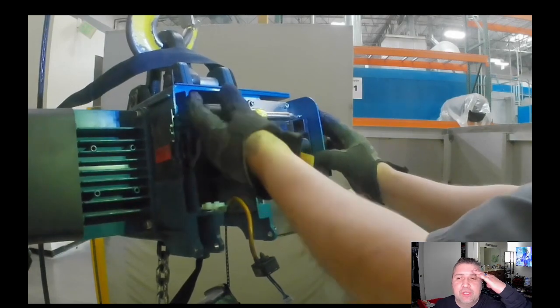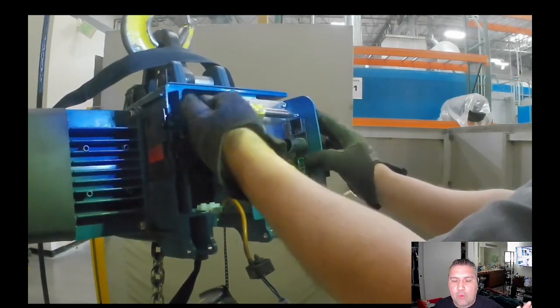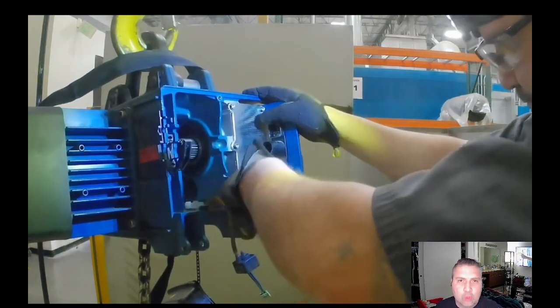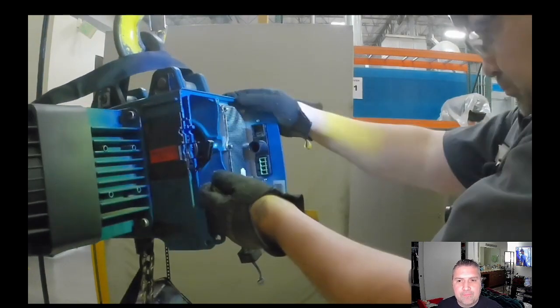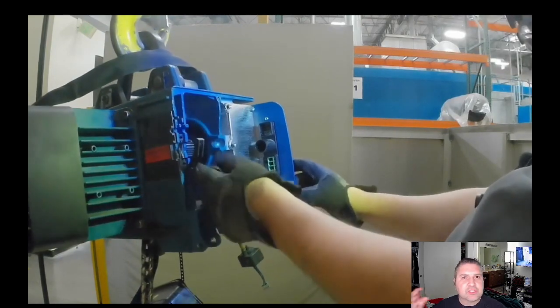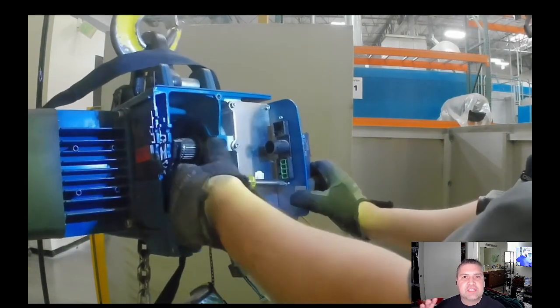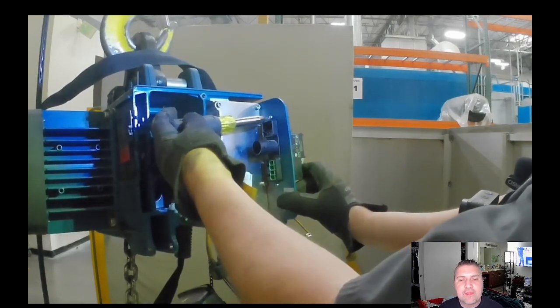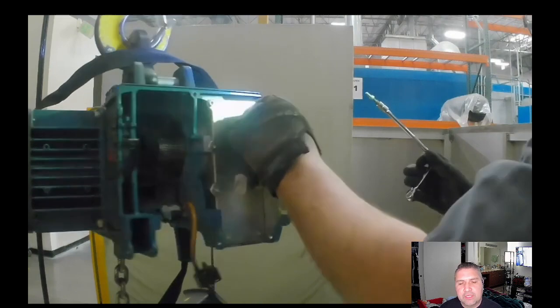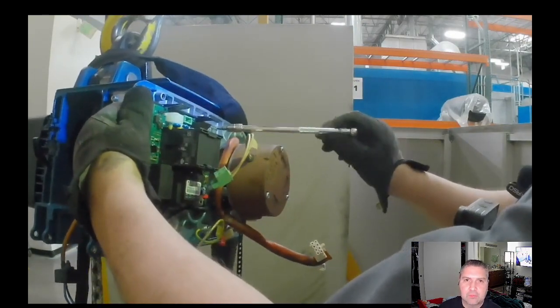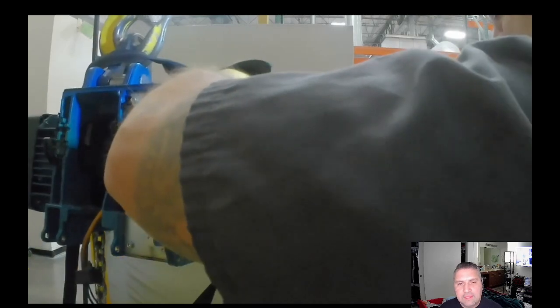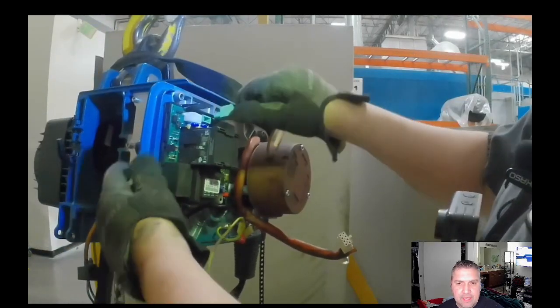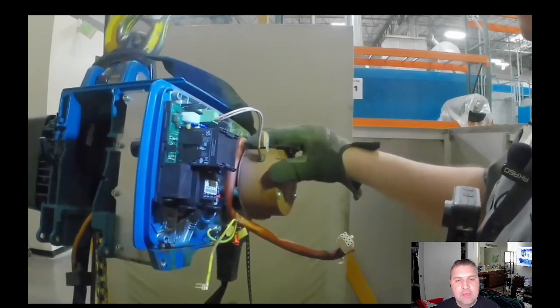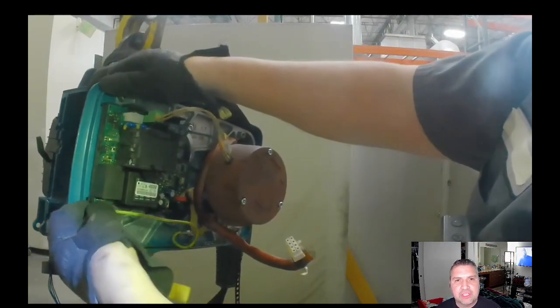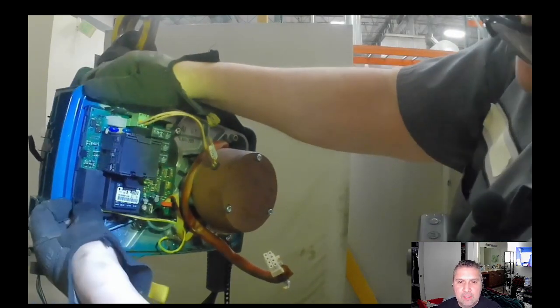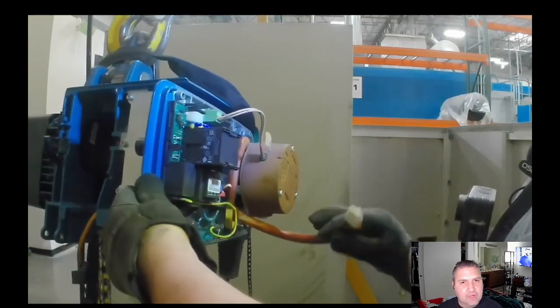A lot of times when you're troubleshooting, if you have a fault that's in question and you have an identical part, sometimes it's easier just to swap it out real quick if it's easy enough, and see if you get any difference of function with a different part. And that's usually always a good method to do if that option is available. And in this case, from what I saw from troubleshooting that board, I was almost positive that the board was bad, but I just wanted to go ahead and do a final determination. I was ready to call this board bad, but if I had the option to just double check and verify, it's even better.